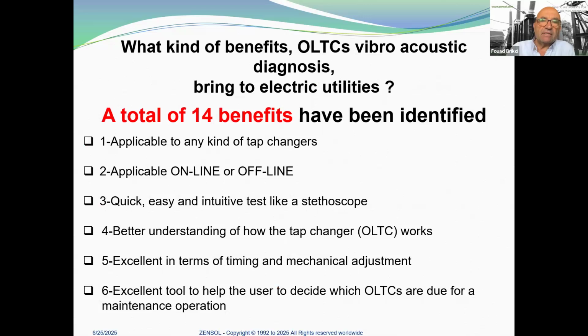So what kind of benefits does OLTC vibroacoustic diagnostics bring to electric utilities? A total of 14 benefits have been identified. I present here only 6. First, it is applicable to any kind of tap changer. Second, it can be used online or offline. Third, it is a quick, easy, and intuitive test, like a stethoscope. The fourth point is that it forces us to better understand how the tap changer works. And it is excellent in terms of timing and mechanical adjustment. And also it is an excellent tool to help the user decide which OLTCs are due for a maintenance operation.